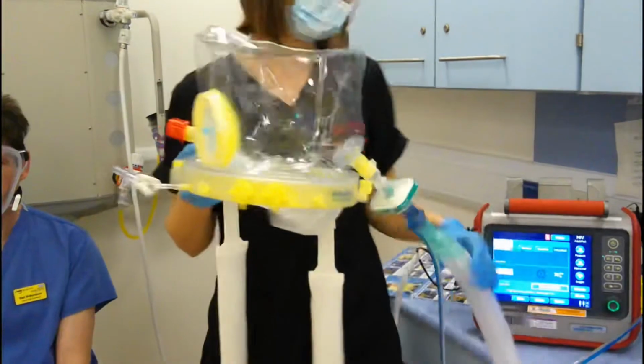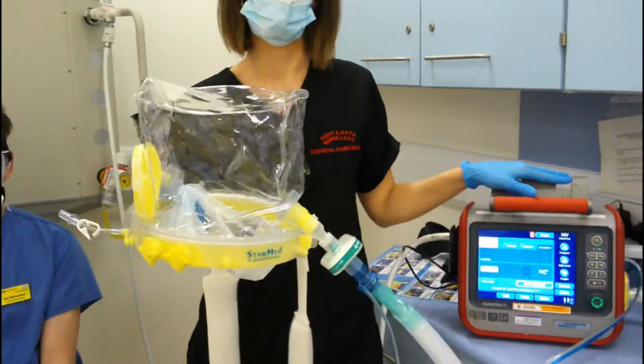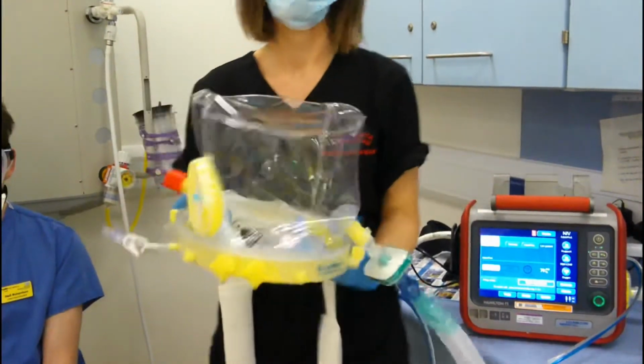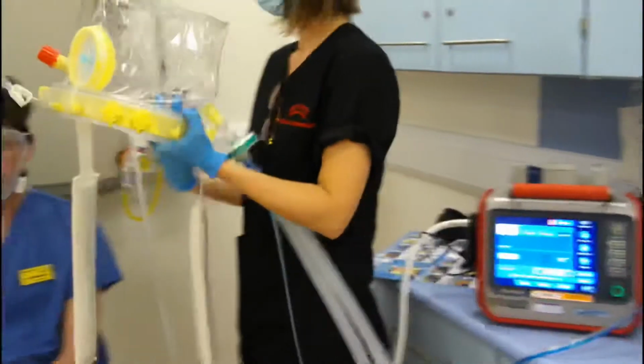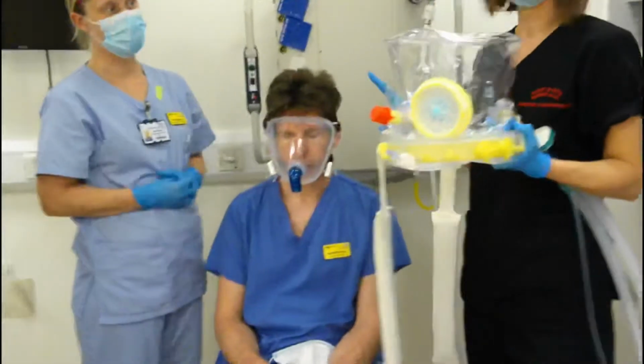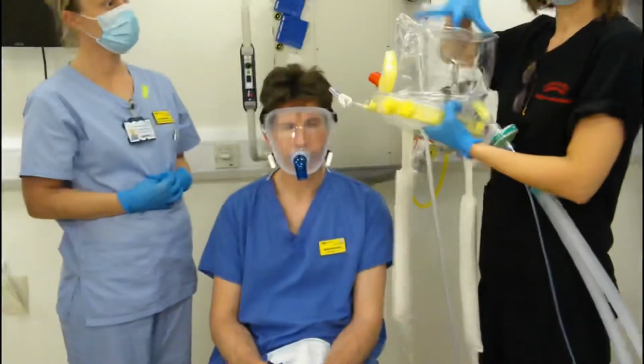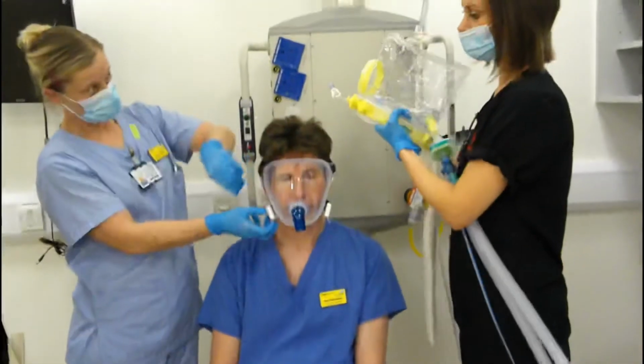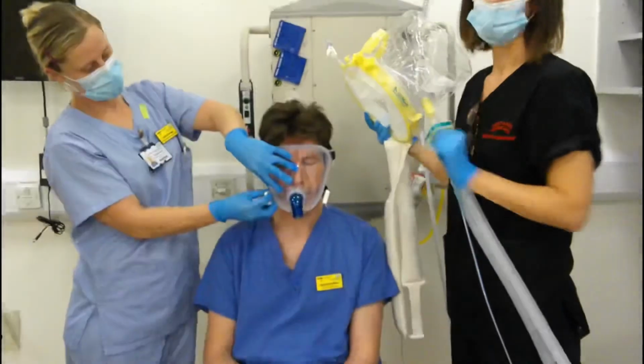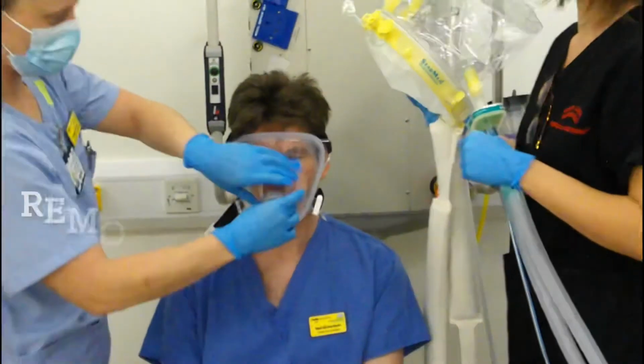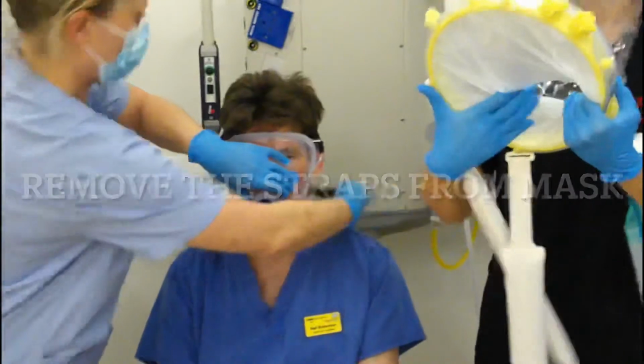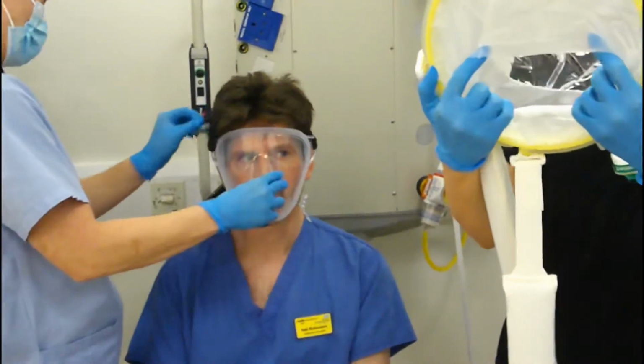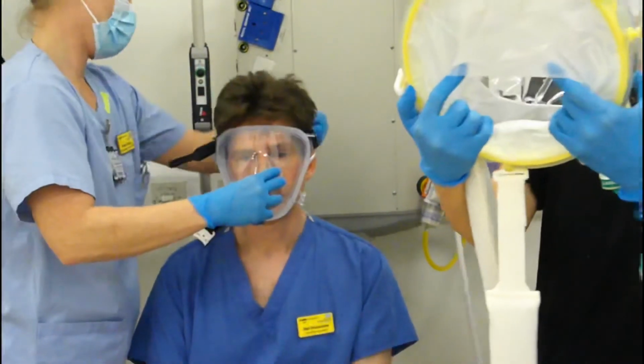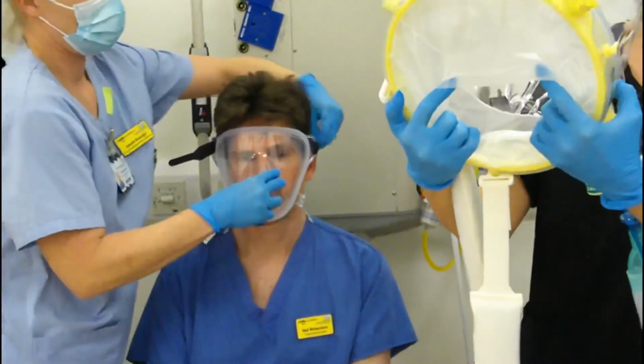I would now start the ventilator on the settings that are appropriate for the patient, and then we will require 3 people to put the hood in place. So most patients normally have a BiPAP CPAP mask already in place. So while this ventilator is running, what I will do is have one assistant who will unstrap but hold the mask over the patient. 2 more of you will then open up the seal at the bottom of the hood to put over the patient's head, and we then do a quick exchange.